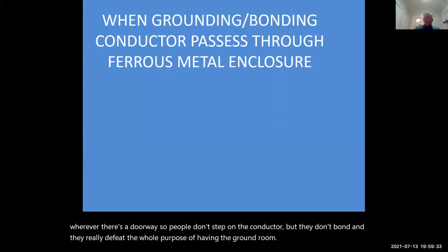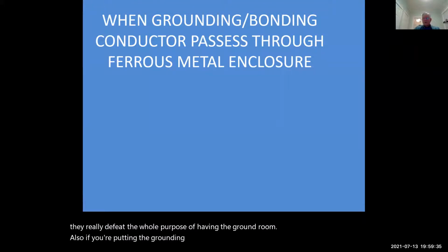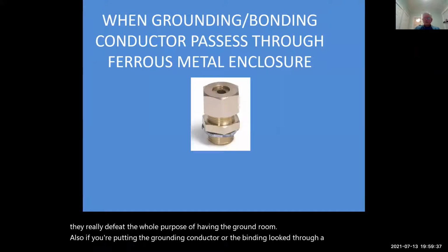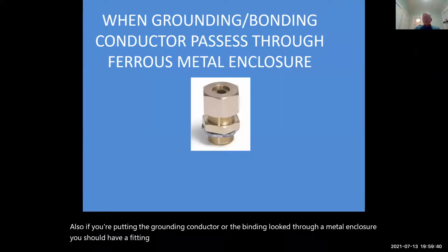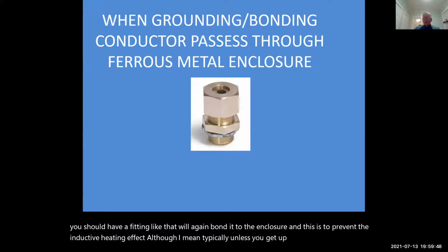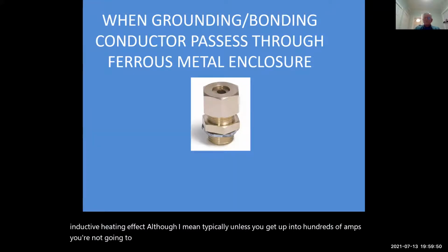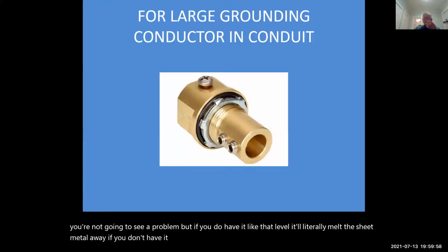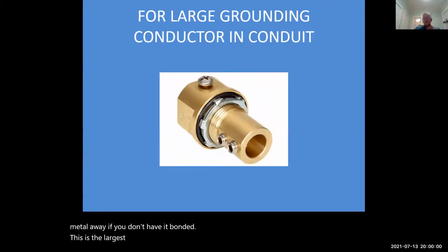Also, if you're putting the grounding conductor or the bonding conductor through a metal enclosure, you should have a fitting that will again bond it to the enclosure. This is to prevent the inductive heating effect. Although typically, unless you get up into hundreds of amps, you're not going to see a problem. But if you do have it at that level, it'll literally melt the sheet metal away if you don't have it bonded. This is the larger size if it's in conduit.